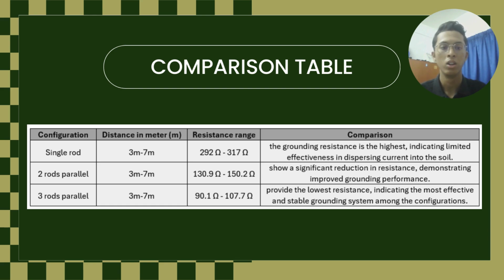It shows a significant improvement by simply adding a second rod. We have cut the resistance by more than half, bringing the range down to 130.9 ohm until 150.2 ohm. This demonstrates a much improved grounding performance.